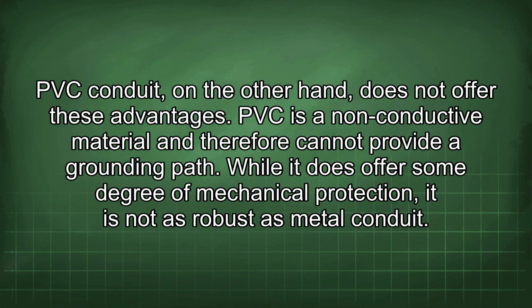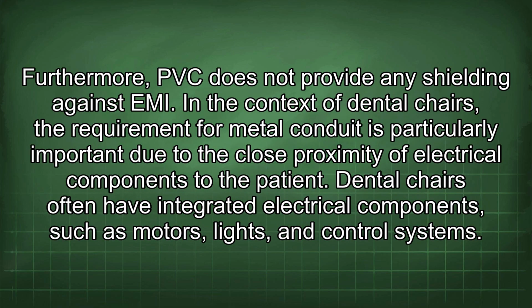PVC conduit, on the other hand, does not offer these advantages. PVC is a non-conductive material and therefore cannot provide a grounding path. While it does offer some degree of mechanical protection, it is not as robust as metal conduit. Furthermore, PVC does not provide any shielding against EMI. In the context of dental chairs, the requirement for metal conduit is particularly important due to the close proximity of electrical components to the patient.